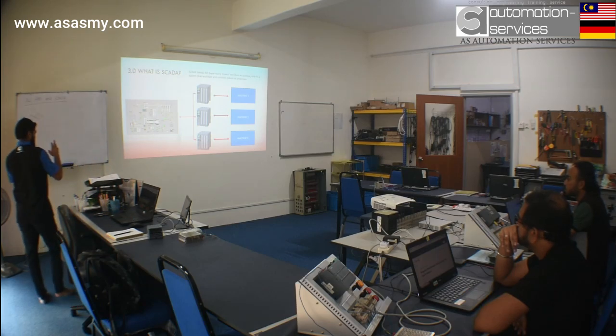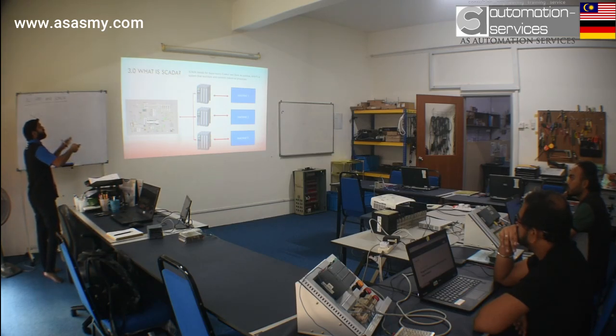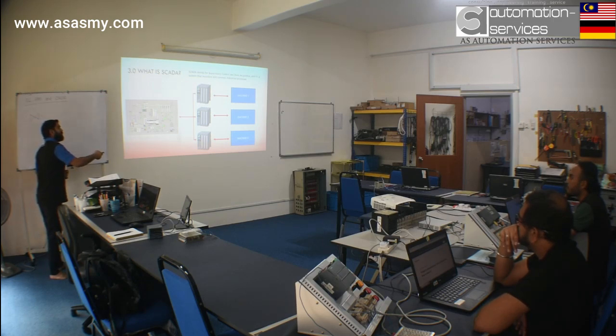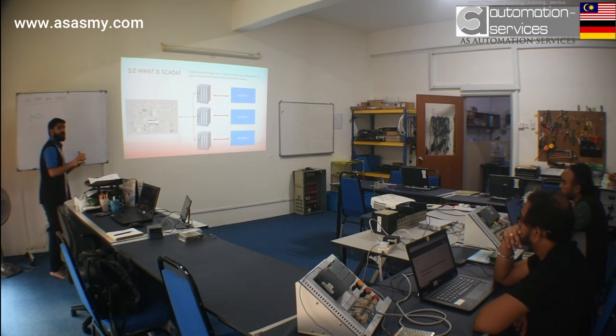But what's special about SCADA is that you can control multiple machines. So for example, this machine has some inputs and outputs, which we put into your SCADA system. This other machine also has some inputs and outputs, and so does this one. You don't necessarily need to show all the inputs and outputs - you choose which input and which output you want to show in the SCADA.